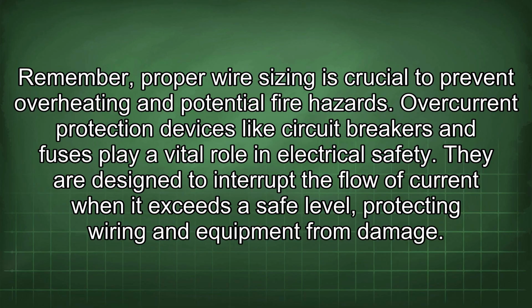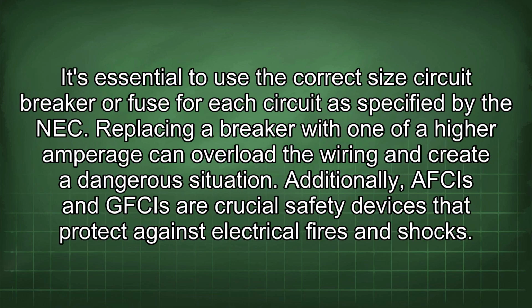Overcurrent protection devices like circuit breakers and fuses play a vital role in electrical safety. They are designed to interrupt the flow of current when it exceeds a safe level, protecting wiring and equipment from damage. It's essential to use the correct size circuit breaker or fuse for each circuit as specified by the NEC. Replacing a breaker with one of a higher amperage can overload the wiring and create a dangerous situation.